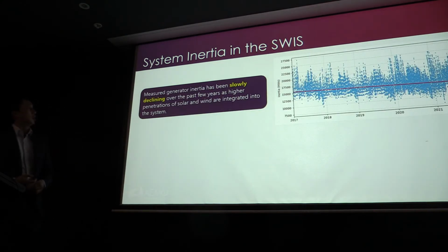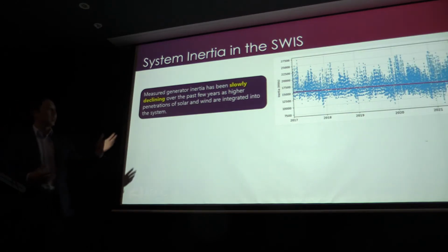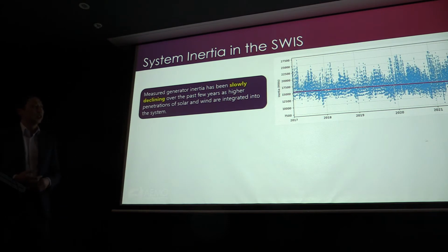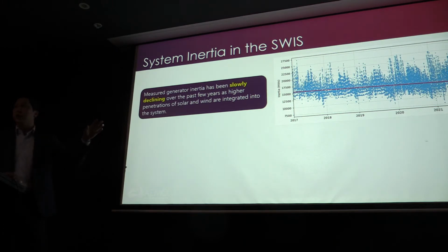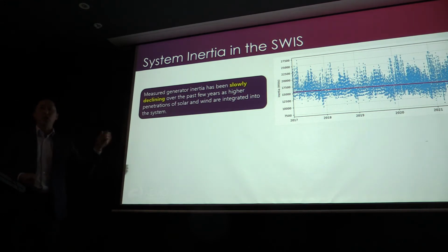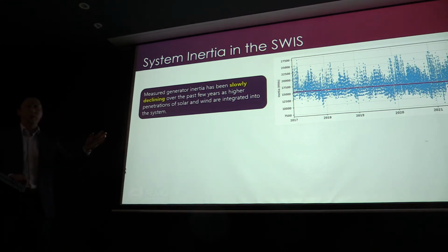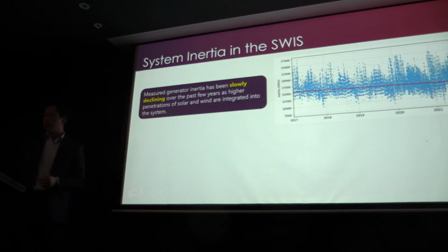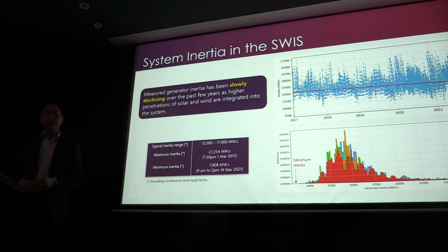And not only is it low, but it's been going lower over the years. So here's a plot from 2017 to basically now, August 2021, and you can see it's really slowly declining. And I will say this is generator inertia, so it's not even looking at load inertia or anything, we're just talking about generator inertia, and I'll talk about that a bit more. And it's been declining because of increased penetration of inverter-based resources, solar and wind, that is coming into the system, and a lot of rooftop PV.